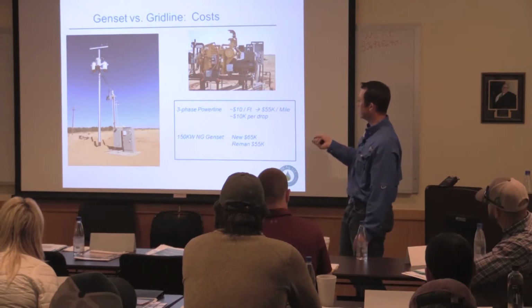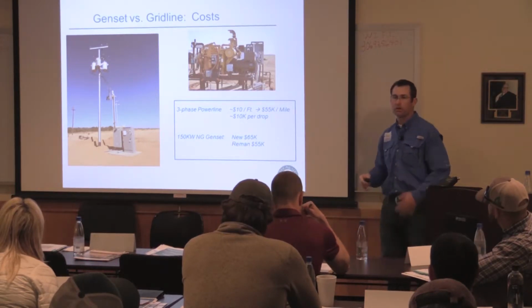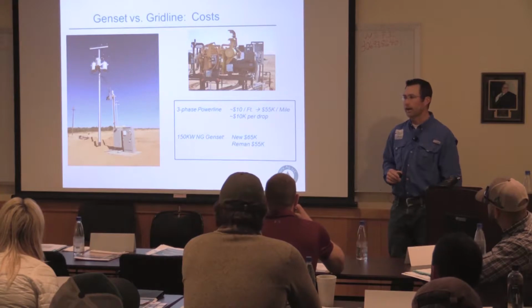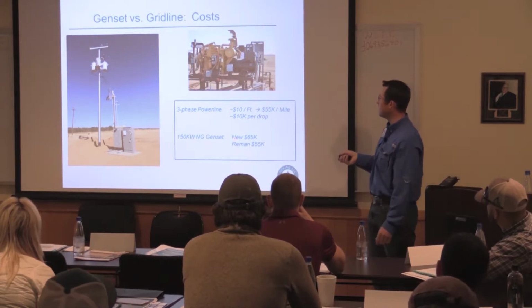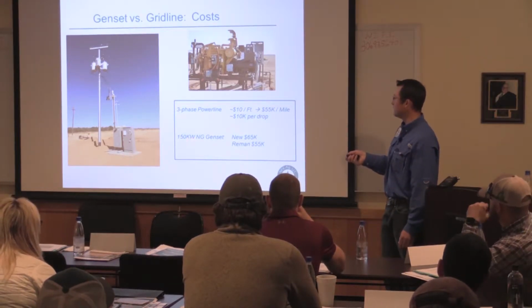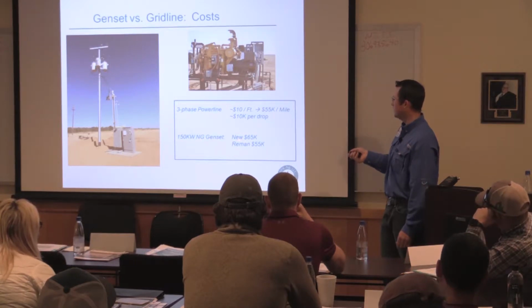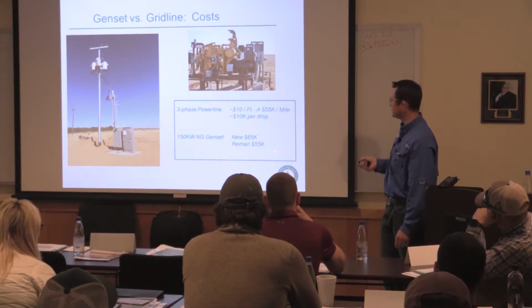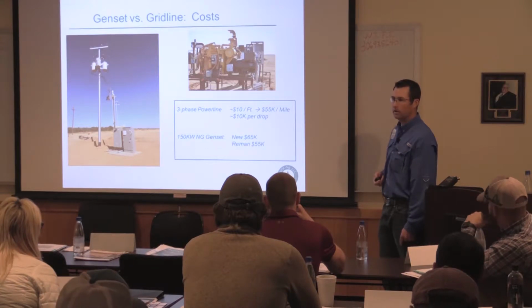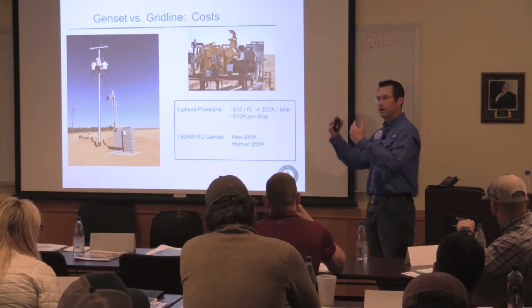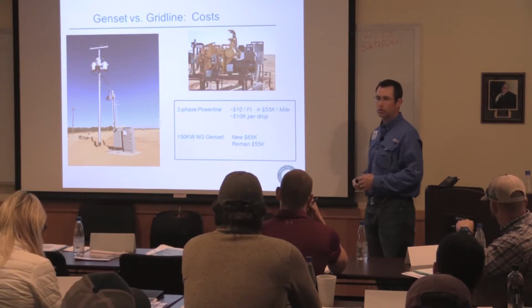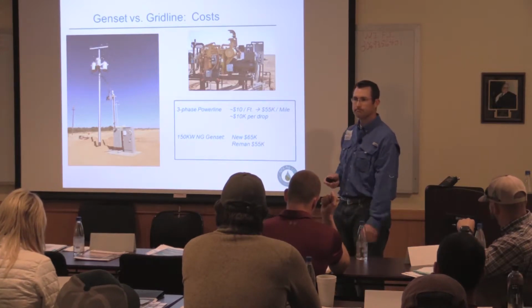And I'm estimating this off of a 200 amp service coming in, which is basically the size you're looking at. If we take that same loading, the 150 kilowatt natural gas genset, new, you're looking at $65,000, a reman, you're looking at $55,000. And that's going to be a complete unit on a skid. These particular prices include a radiator and a fan and all of that.